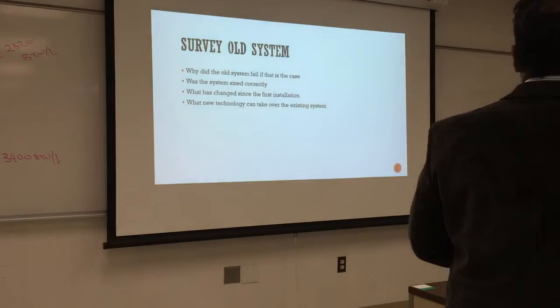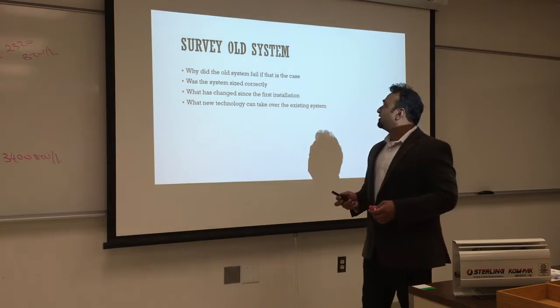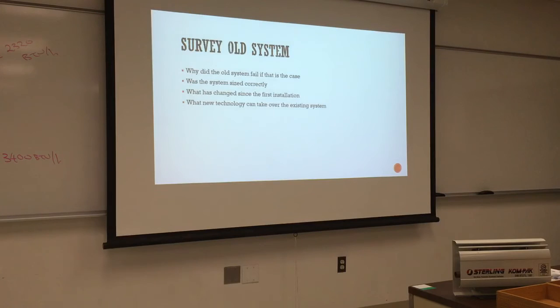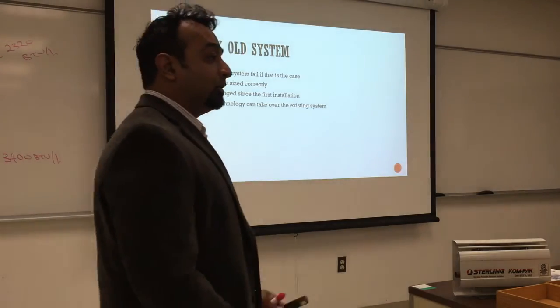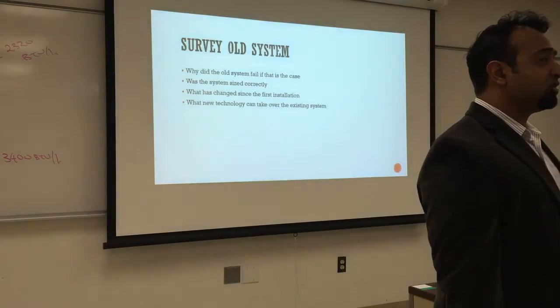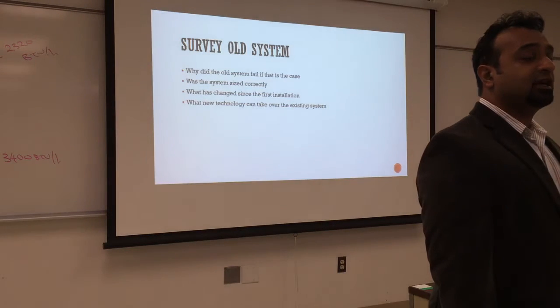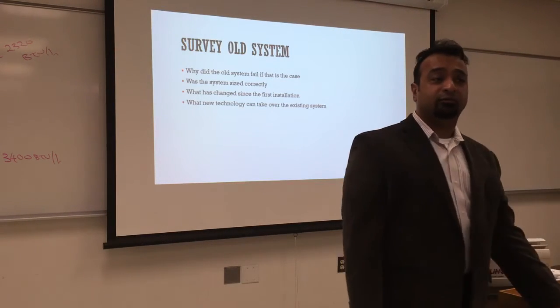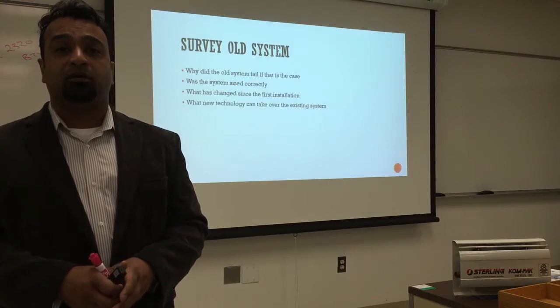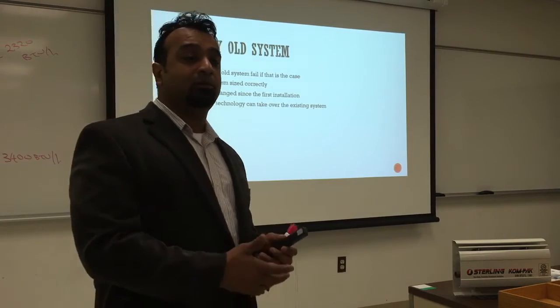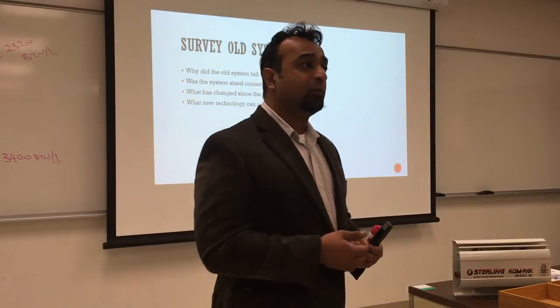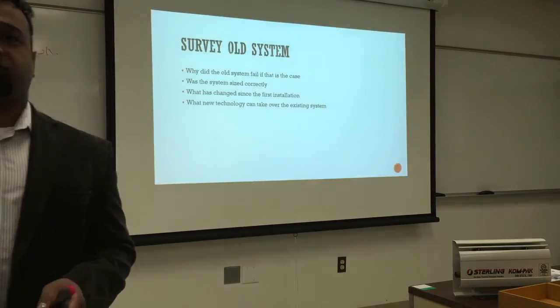First of all, why did the old system fail? If somebody comes to you and wants you to replace a boiler, ask: how old is it, when was it installed, is it rusted, why is it rusted? Look for acidic condensation in the chimney—maybe it wasn't well ventilated. Check for water leaks and humidity accumulation in the boiler. Survey the system first and know: was it installed properly, was it performing adequately, how and why did it fail?